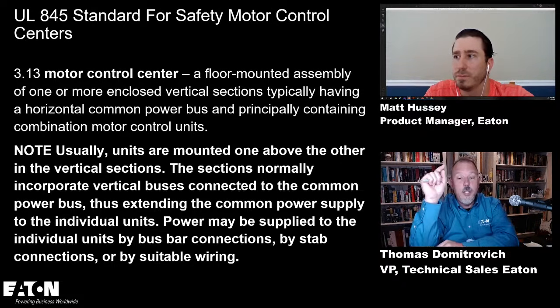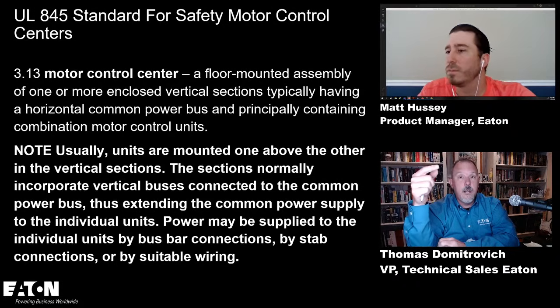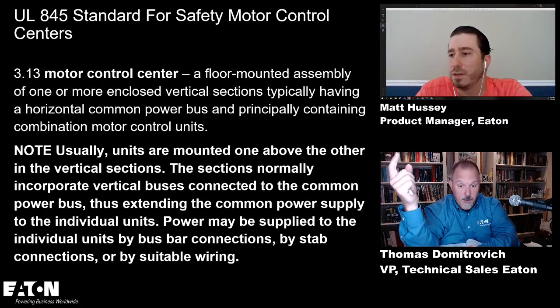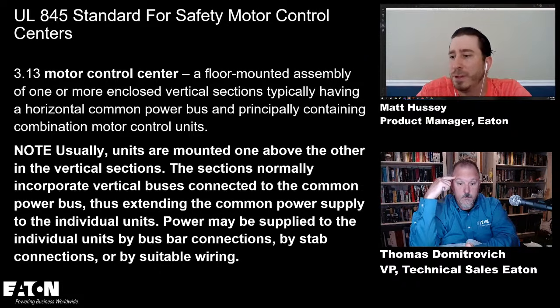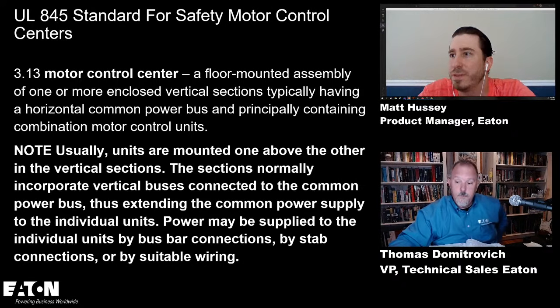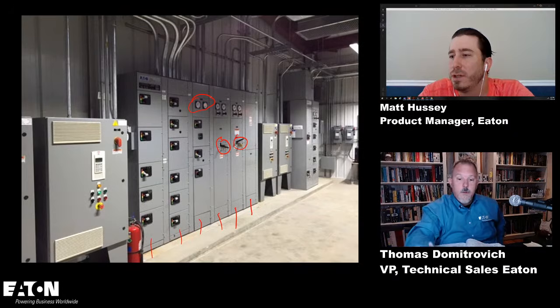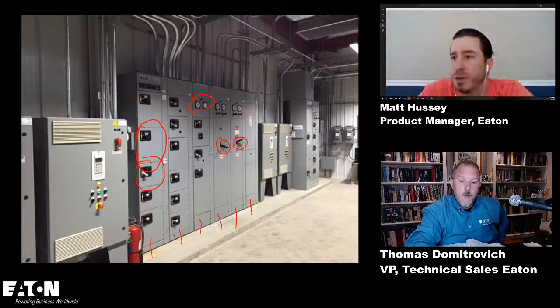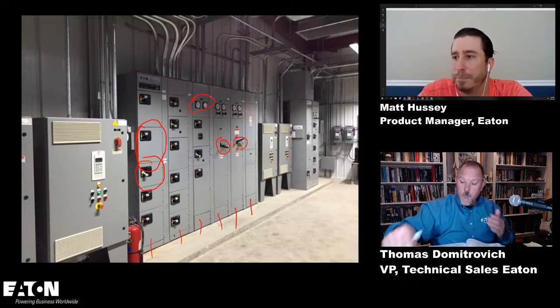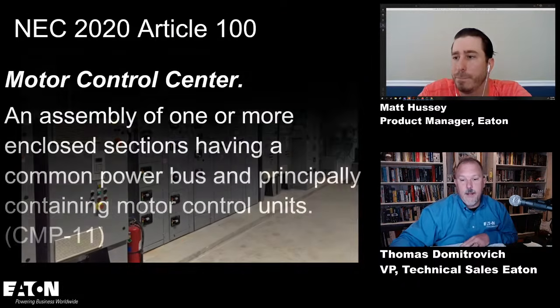That's an important thing. So now it says usually units are mounted one above the other in the vertical section. So when they say units, we know those in industry terminology as a bucket, right? Yeah, you'll commonly hear that used to describe it because it's really kind of self-contained. So each one of these is a unit. Yeah, each one of those compartments. Behind each one of those units, they're capable of being withdrawn, inserted, removed, with a plug-on connection to the bus. Okay, so each one of these has a bucket that can be removed, and we'll talk more about the different innovative things that people are doing in that area. But okay, so I get that down.